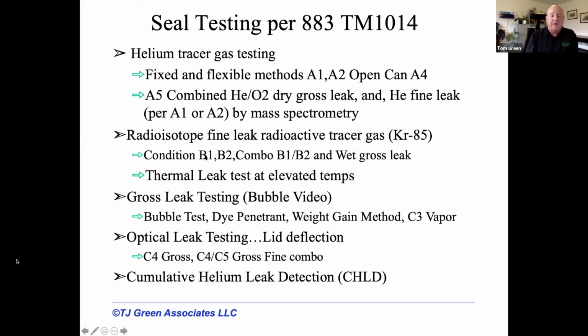There's a radioisotope method, but in the medical community, just because of that word radioactive, it doesn't get a lot of attention. We have our bubble test. I love the bubble test. If I have a chance here, maybe I'll show you a video. It tells you where the leak path is. When you fail a helium hermeticity test, you don't really know where it's leaking from. But the bubble test, which is for gross leaks, is like your bicycle tire that's bubbling. And then there's another methodology, optical leak testing, which has a lot of advantages. There's no helium pressurization cycle. You don't have to bomb it. That's a big advantage because you don't have to worry about residual helium and so forth. And finally, there's a cumulative helium methodology that's listed in there.